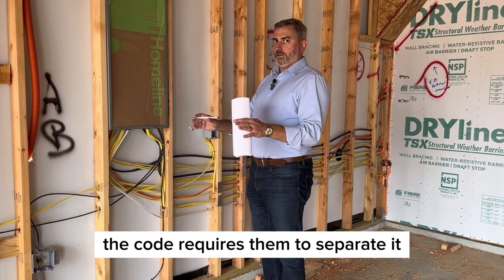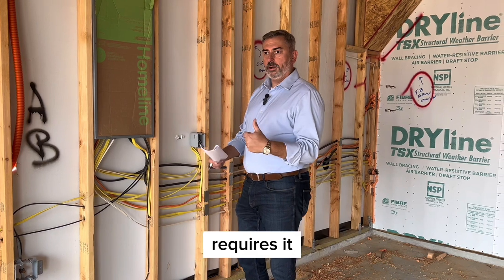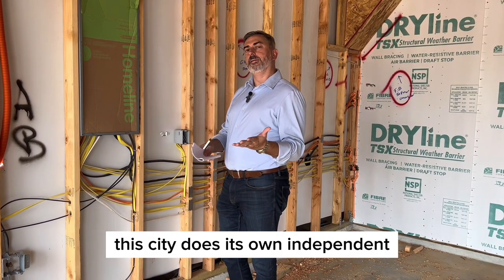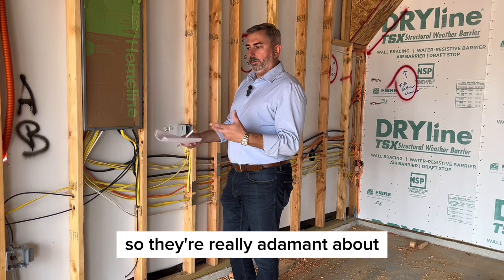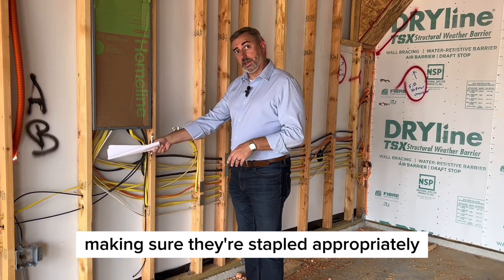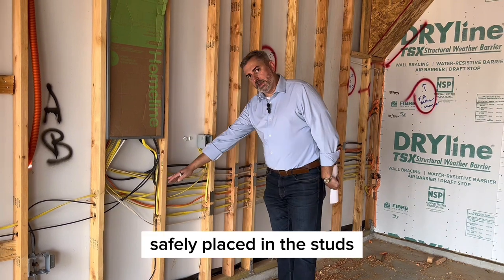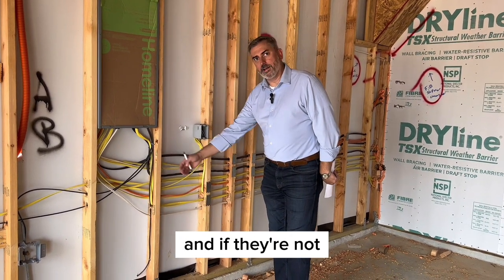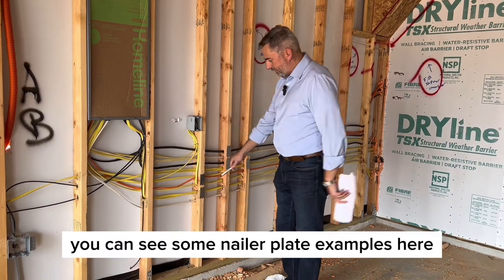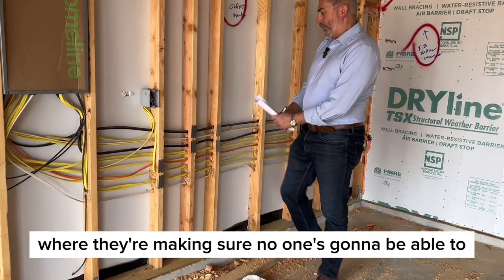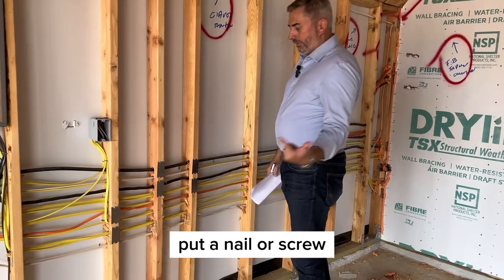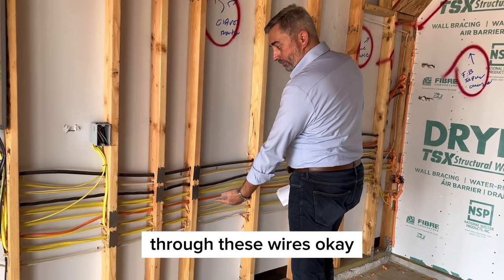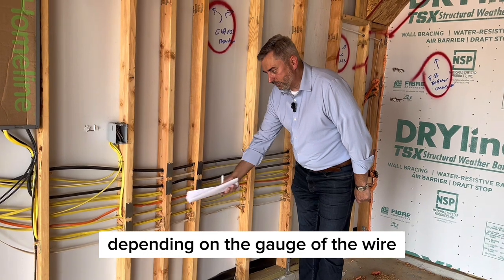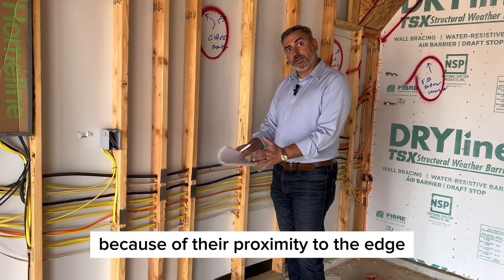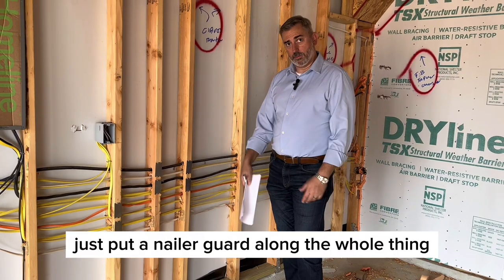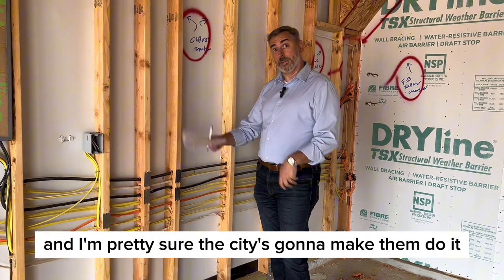Code requires them to separate the wires, though not every municipality requires it—this city does its own independent inspections, so they're adamant about making sure wires are stapled appropriately and placed safely far enough back in the studs. If not, they put nailer plates—you can see some examples here—to make sure no one can put a nail or screw through these wires. Depending on the gauge of the wire, this is required because of proximity to the edge. Best practice is to just put a nail guard around the whole thing, and I'm pretty sure the city will make them do it.